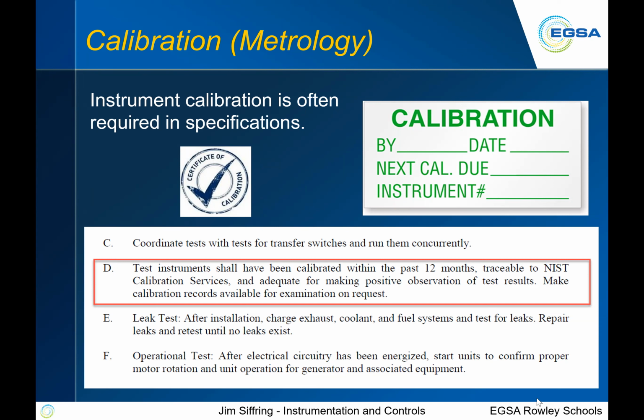So what does that mean? It means that if you go out with your multimeter and test the voltmeter on that genset, and you say yes, that voltmeter is reading correctly, you have to have your meter calibrated by somebody, and that calibration laboratory has to be traceable back to NIST, which in turn goes back to the French BIPM lab. That way we know that everything is calibrated against a known standard, and we're not going to have any of the issues that may arise with equipment that doesn't read out correctly.